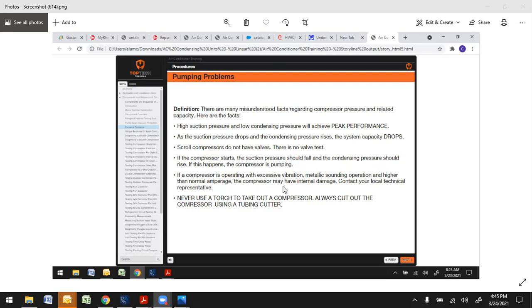If a compressor is operating with excessive vibration, metallic sounding operation, or higher than normal amperage, the compressor more than likely has internal damage and you'll have to get a new compressor. There again, it is highlighted, never use a torch to take out a compressor. Always cut it out with a tubing cutter.